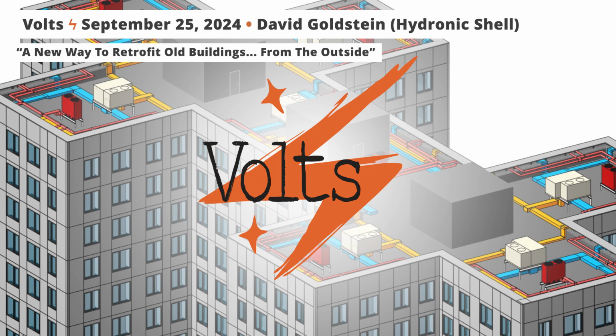Each room will have its own thermostat, a wireless one on the wall. We do wireless because the idea is to be non-invasive, you don't want to run wires through a space. That thermostat tells two things to the unit: it tells the valve to open or close depending on whether it needs water, and it controls the fan speed.